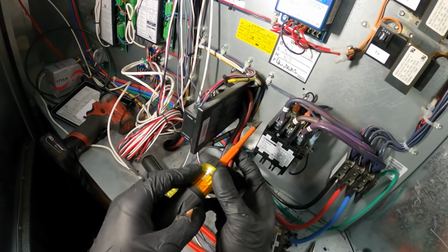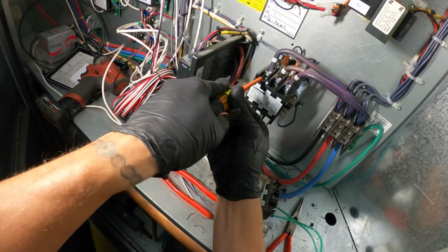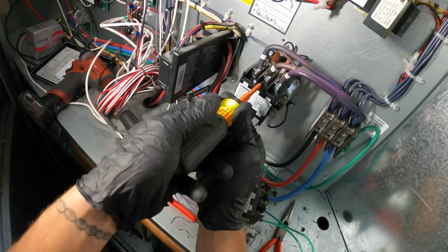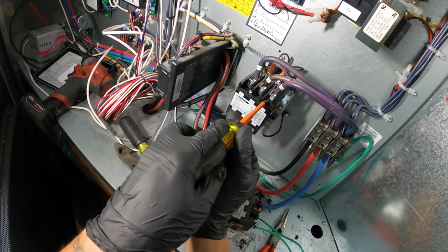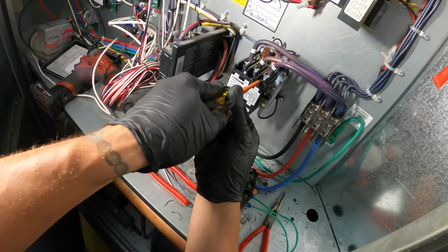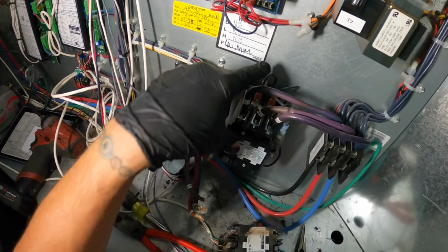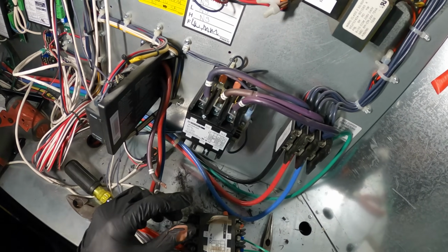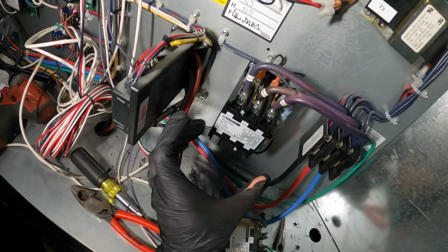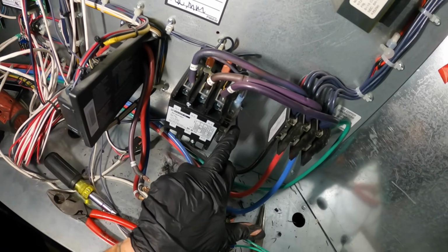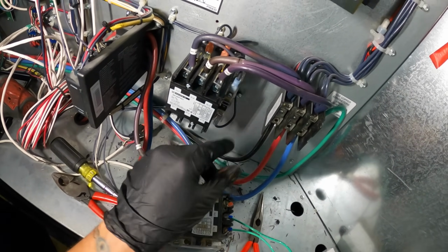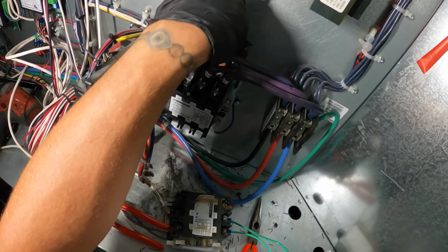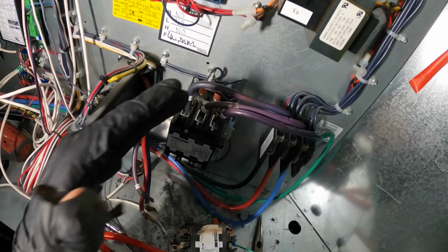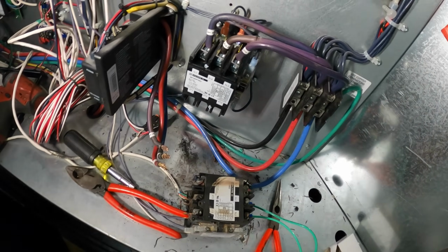Anyways, all right, make sure it's all nice and tight. Coil wires are done, it's always in the back for this style of contactors. For a 2-pole, it's on the sides. Auxiliary, everything is good, nice and tight, good connections. Coil, line voltage, and auxiliary.